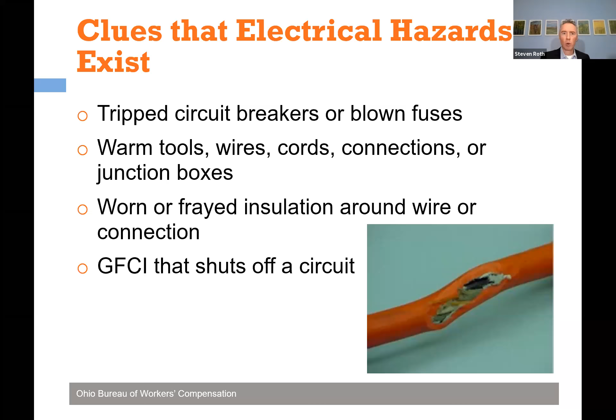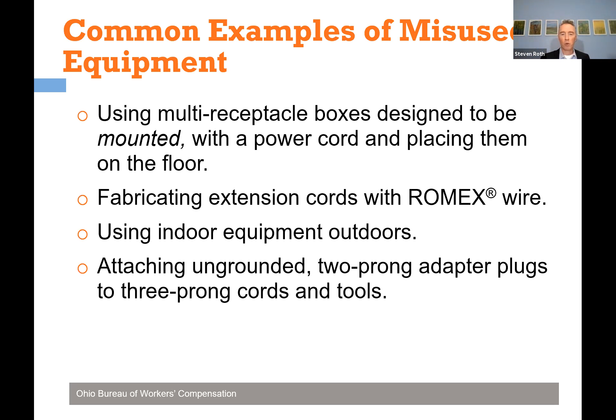We see this all the time - a lot of misuse of equipment. Fabrication of extension cords using Romex cables, which isn't flexible cabling, or vice versa, using flexible cabling to make a permanent installation. We see both, and they're both wrong. Using equipment labeled for indoor use outdoors is not in accordance with its label and listing. And then attaching these little 2-prong adapter plugs - this side has the ground, this side does not - so now permanent and continuous has been removed. Another very common mistake.